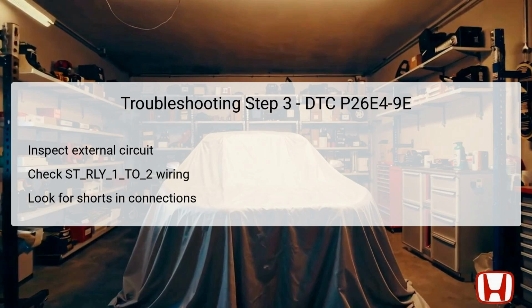Additionally, use a multimeter to check for continuity and resistance in the wires, ensuring they exceed the minimum values required for proper operation. If abnormalities are detected during this inspection, repairs or replacements may be required. Conducting this inspection systematically will help eliminate wiring issues as a source of the DTC.